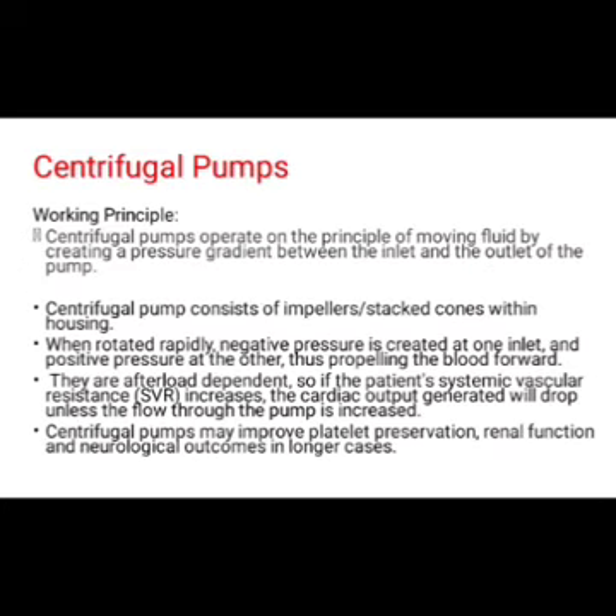Centrifugal pumps, their working principle. Centrifugal pumps operate on the principle of moving fluid by creating a pressure gradient between the inlet and the outlet of the pump. A centrifugal pump consists of impellers, stacked cones within a housing. When rotated rapidly, negative pressure is created at one inlet and a positive pressure at the other, thus propelling the blood forward. They are afterload dependent, so if the patient's systemic vascular resistance increases, the cardiac output generated will drop unless the flow through the pump is increased. Centrifugal pumps may improve platelet preservation, renal function, and neurological outcomes in longer cases.